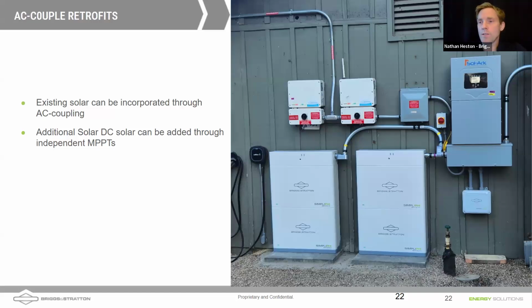Daniel, what's different about the Sol-Ark? Is it grid following? Is it grid forming? What is it? Grid following, right? So what we need is a Sol-Ark to form a grid so that the SolarEdge or Enphase micro or string inverters will think that nothing's different and the grid is still there, and they'll continue to output. Yeah, so the Sol-Ark inverter can be grid following and it can also be grid forming, right? And so in the event of a grid down situation, that Sol-Ark inverter can form a grid using power from the batteries, and that formed grid can then be latched onto by those string inverters.